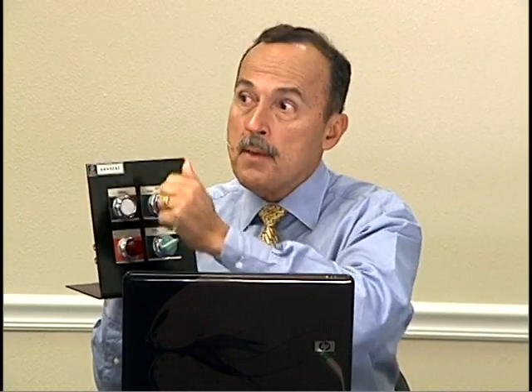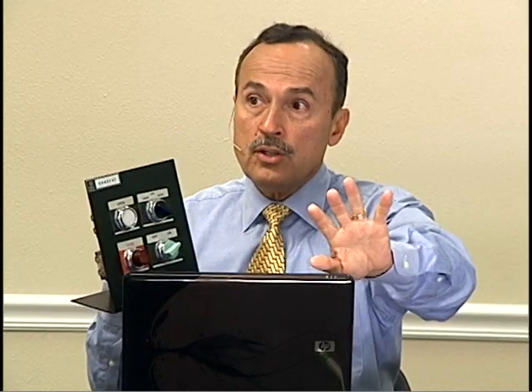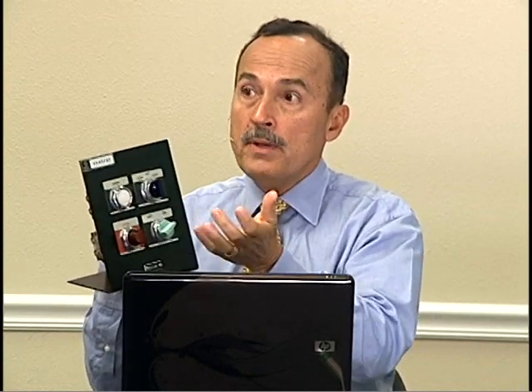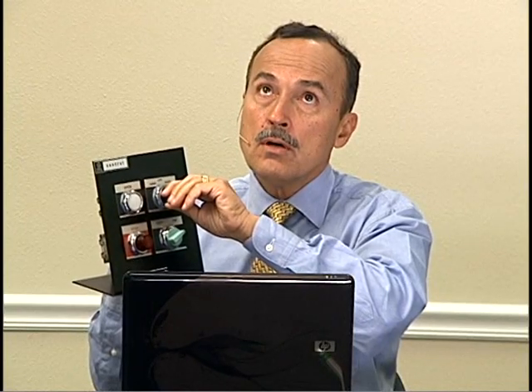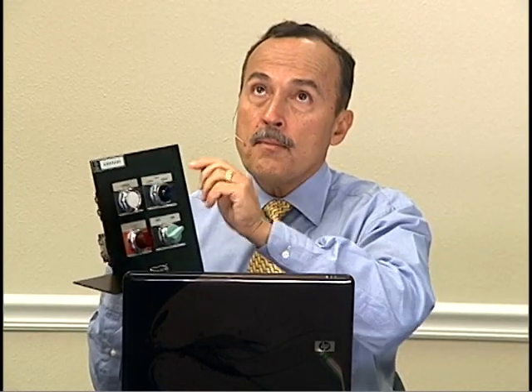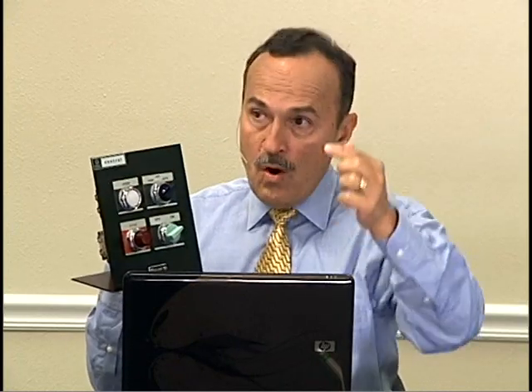So now, without getting in the circuit yet, if I'm in the hand, hand-operated, in the manual mode, I'm obviously getting power from line 1 to my coil. Right. I'm bypassing all the controls. That's a two-wire control circuit, right? Yeah, right there, exactly. When I go to off, I'm basically having a stop button that's open. There's no power going anywhere. Right. When I go to auto, you bring in all your control devices. Now I'm bringing in from the line 1, I'm now going to my 3-wire control circuit.